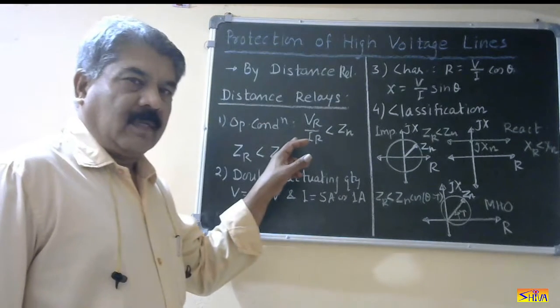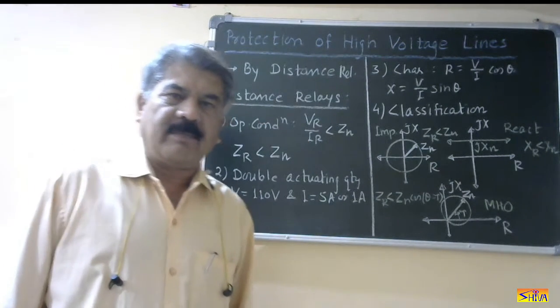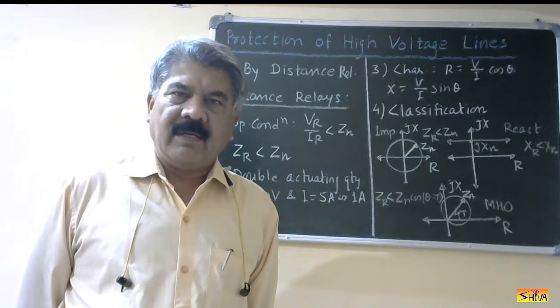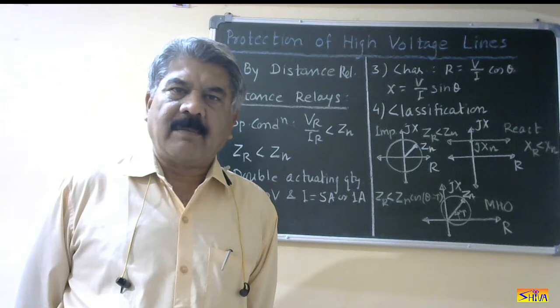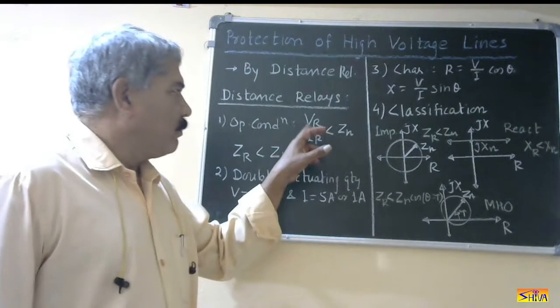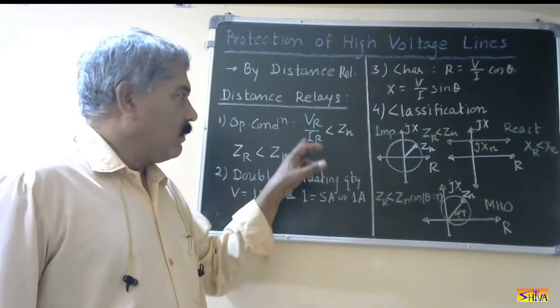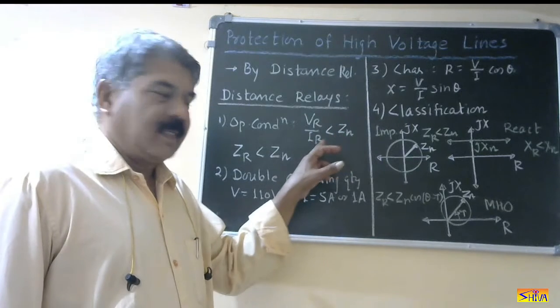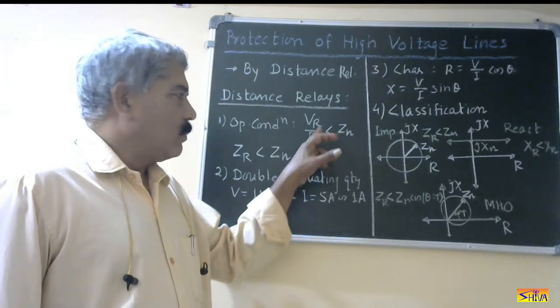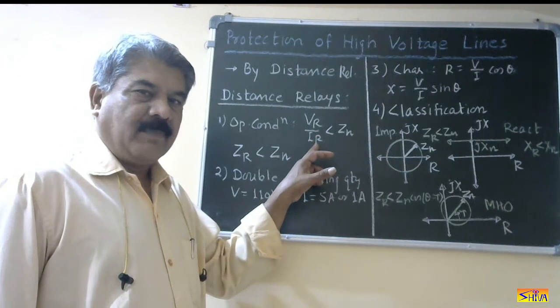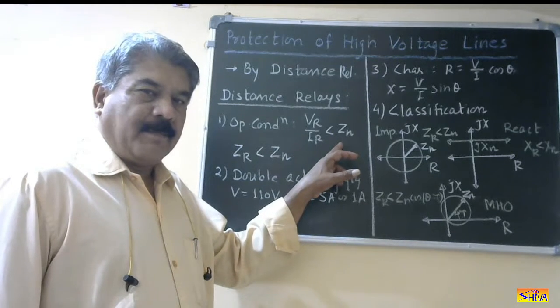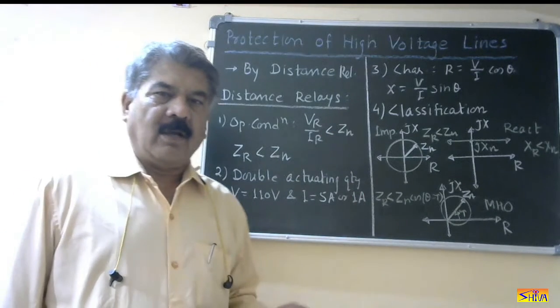The first point is regarding the operating condition of the distance relays. The definition is: these are relays which operate when the ratio of voltage measured by the relay and current through the relay falls below a certain predetermined value. So the operating condition is Vr upon Ir should be less than Zn. V upon I is a measure of impedance, so if this ratio of voltage measured by the relay and current through the relay is less than the impedance setting of the relay, then the relay operates.